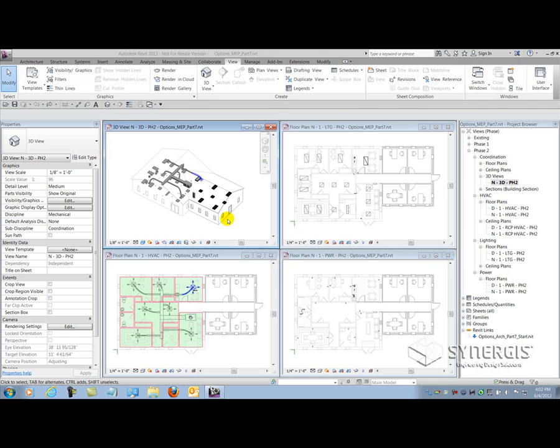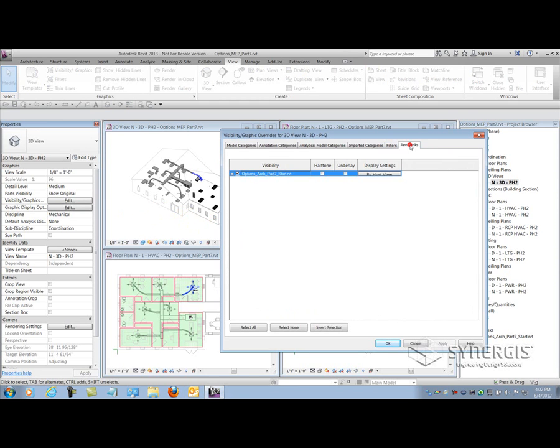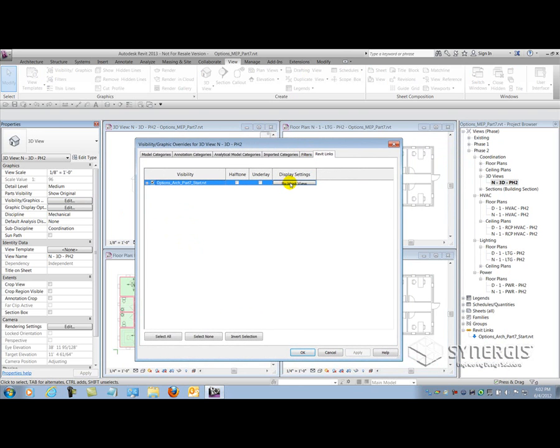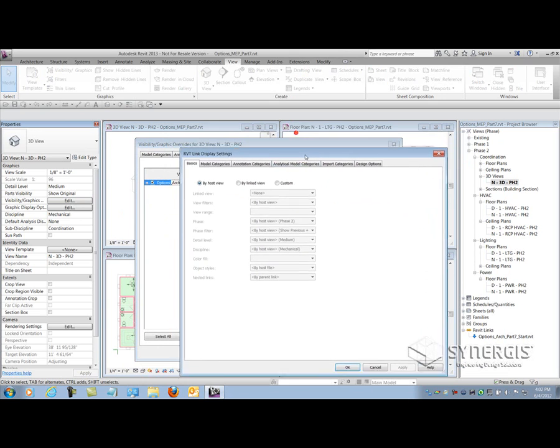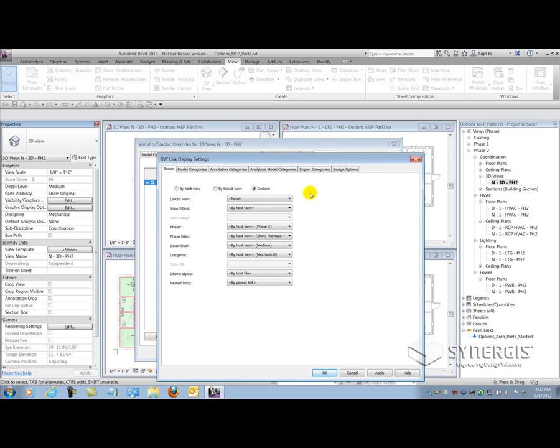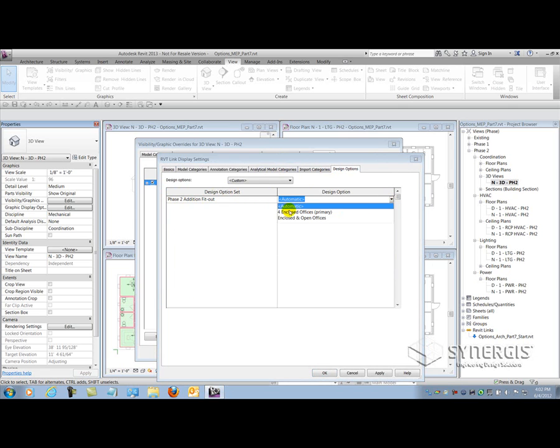The architectural file is already linked in and I can simply go to visibility graphics of any of the views that I see it in and select the Revit links tab in that dialog. I can actually select the display settings button of the link file and set it to custom for the basics tab. Once it's set to custom here, I can explore the design options that the architect has made. Here I can see they made a design option set called Phase 2 Addition Fit-out, and within that option set, they have two options provided. Now that I know about that, I can go create them within my MEP file.